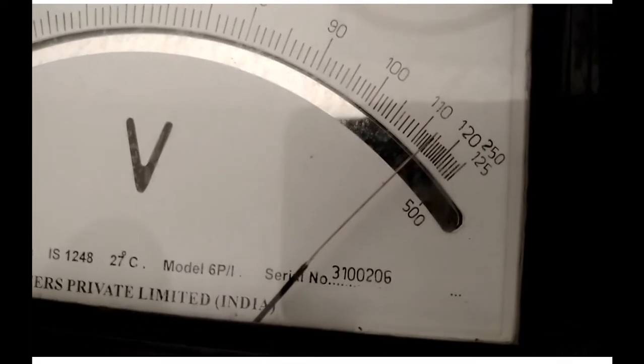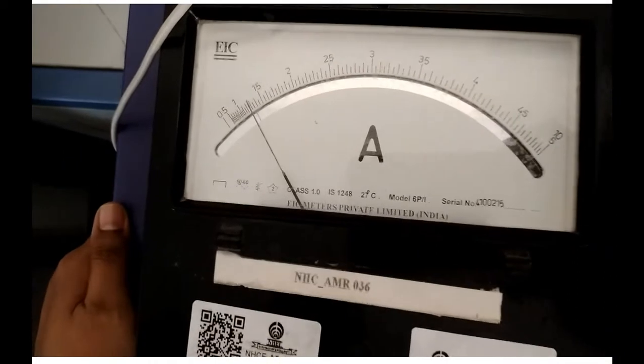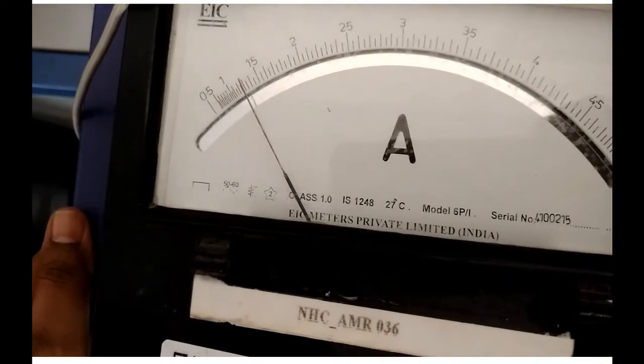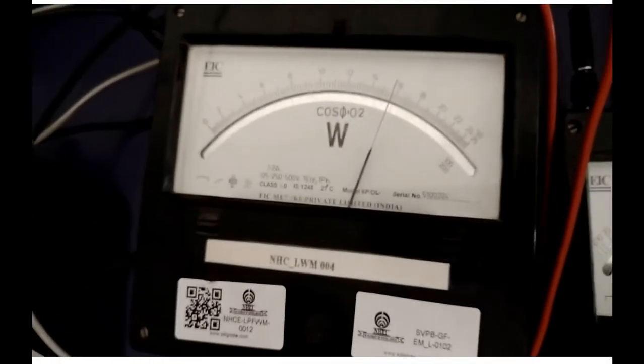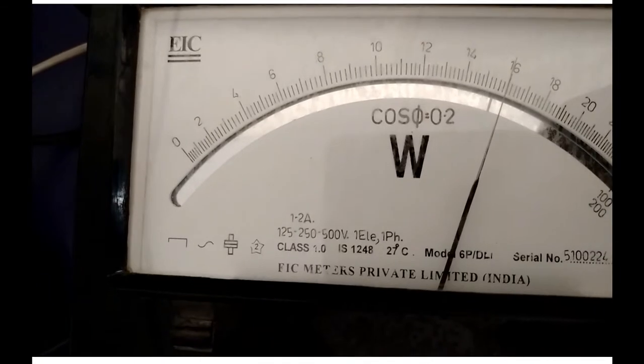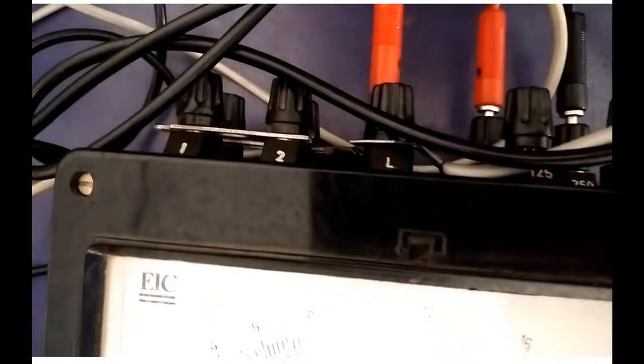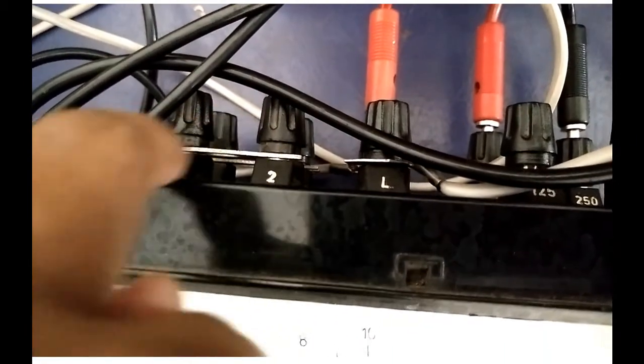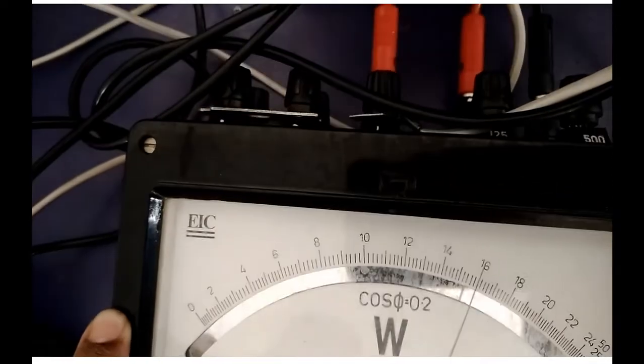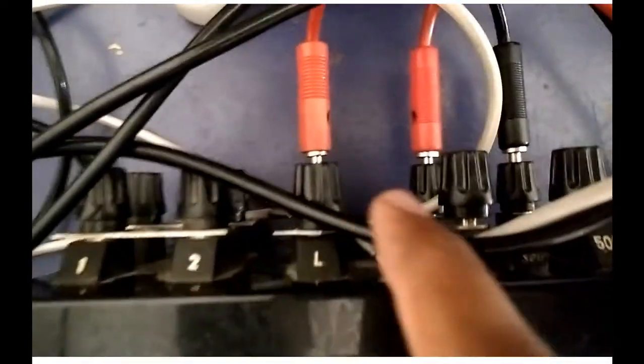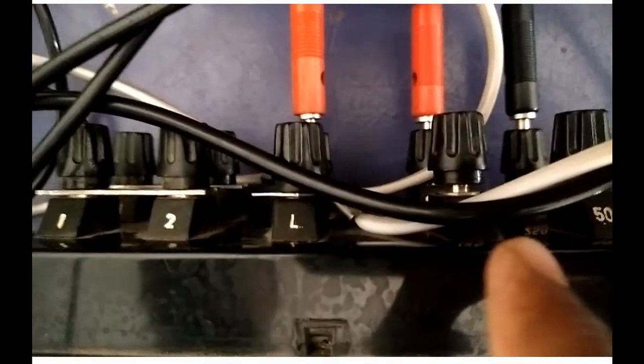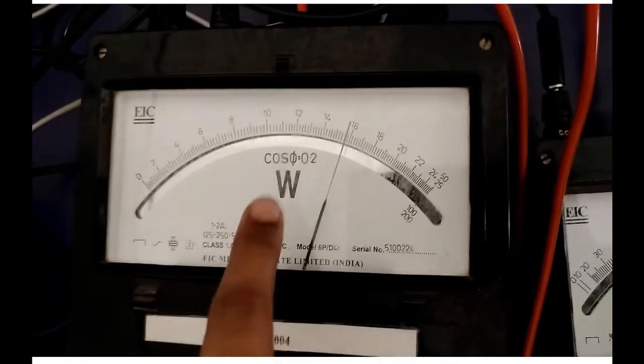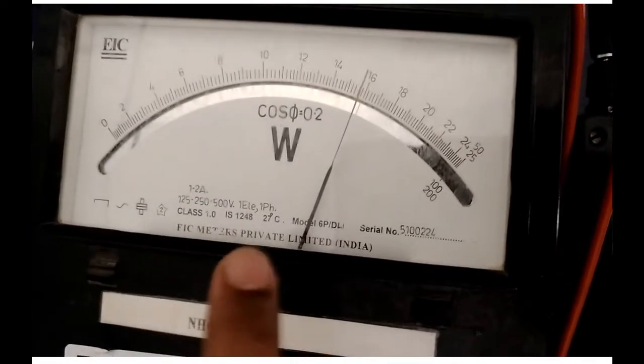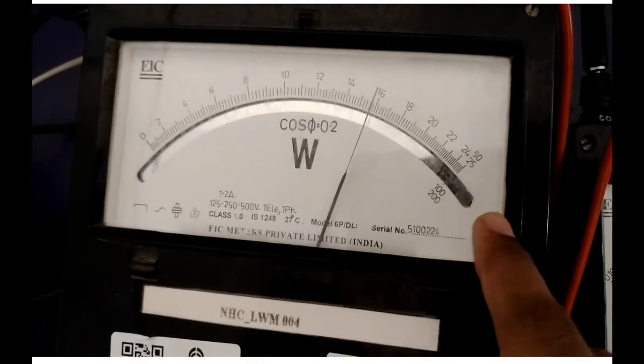We are going to note down this voltmeter reading and the ammeter reading. This gives the no load current, around 1.25 amps. The wattmeter reading we take, 16 into the multiplication factor. The multiplication factor you have to see with respect to the current rating we have chosen. We have connected the 1 to 2 range, so the range is 2 amps, and the voltmeter range is 250. With this voltage and current, and LPF cos phi of 0.2, you use the formula VI cos phi by full scale reading and find out the multiplication factor.